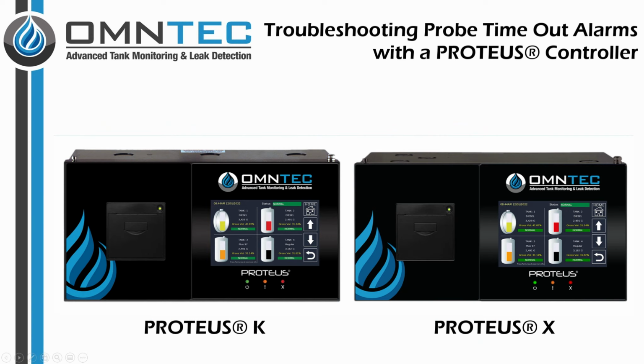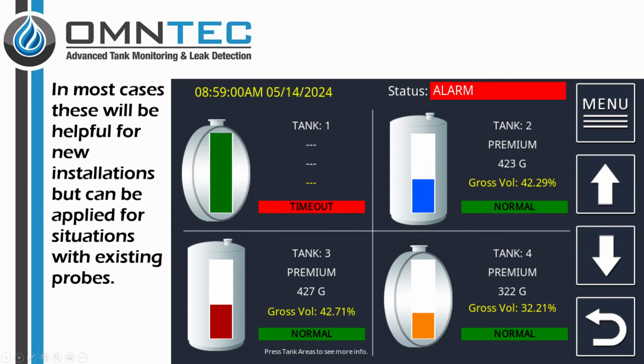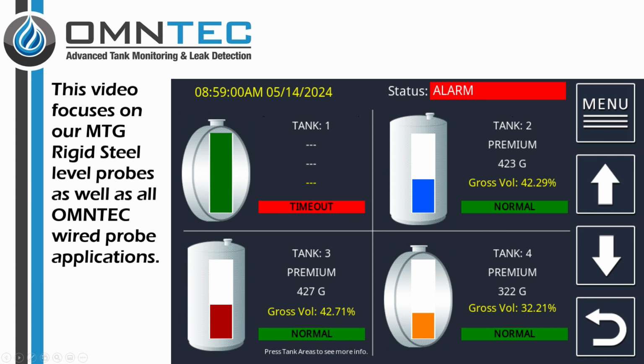This video will detail troubleshooting tips for probe timeout alarms with a Proteus ATG controller with regards to possible hardware issues. In most cases, these will be helpful for new installations, but can be applied for situations with existing probes. This video focuses on our MTG rigid steel level probes, as well as all OMNTEC wired probe applications.